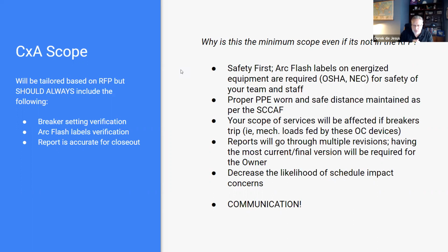Arc flash labels, where do you stop requiring arc flash labels in a distribution system? I usually stop at the last panel in that circuit. So obviously the main incomer, the breakers, down past any distribution panels, transformers, and then down to the last panel. That's usually where we end. We don't go down to the last device or to the last motor, we'll just stop at the last panel in that system. Anyone else have anything they've done differently, or maybe they stop a little higher? It's not usually necessary to go all the way down.